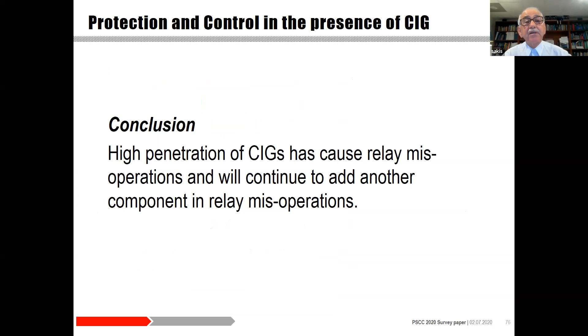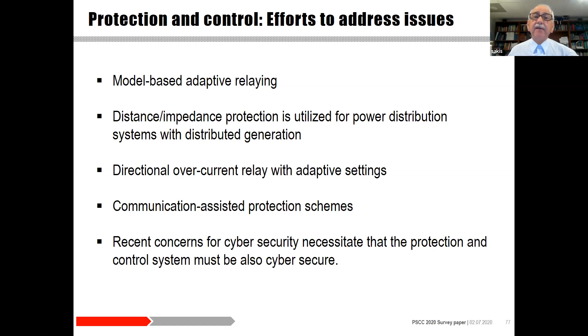At Georgia Tech, and of course elsewhere, there is a lot of research to deal with these problems. You see here a list of various approaches: model-based adaptive relaying, distance impedance protection utilized for power distribution systems with distributed generation, directional overcurrent relays with adaptive settings, etc. These approaches are good. On the other hand, they become very complex. And as I said, complexity brings a lot of additional problems. At Georgia Tech, we've been working in the past few years on a new approach in protection, which will alleviate most of these problems. And the idea of the new approach is very simple.